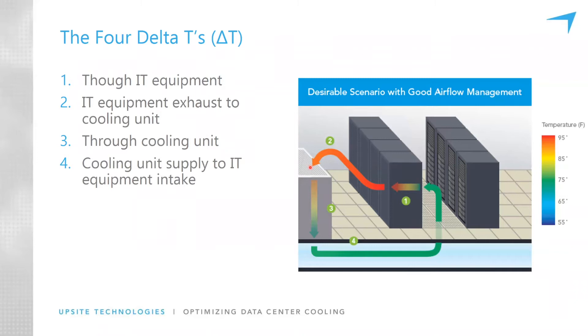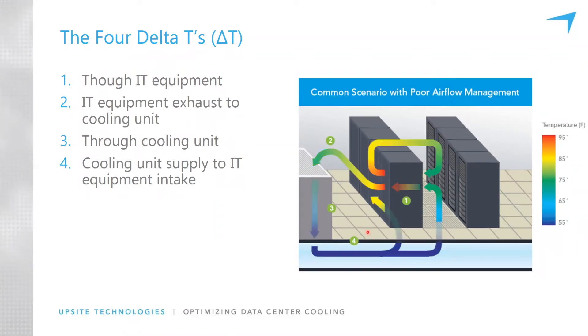You wouldn't think that delta T4 and delta T2 would change very much, and in this example they're drawn at the same temperature. Ideally, air comes out at 75 degrees and the warmest IT equipment intake temperature is maybe 80 to 90 degrees. Air exits IT equipment at 95 or 100 degrees and returns to the cooling units at around 90 to 95 degrees. That is the way we would like to have our facilities.